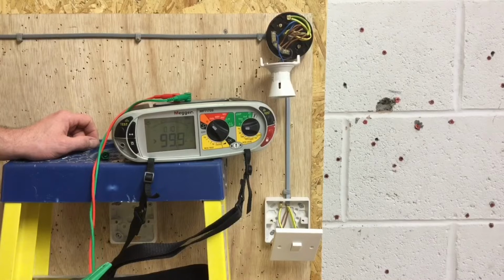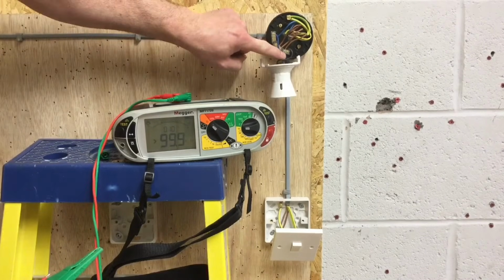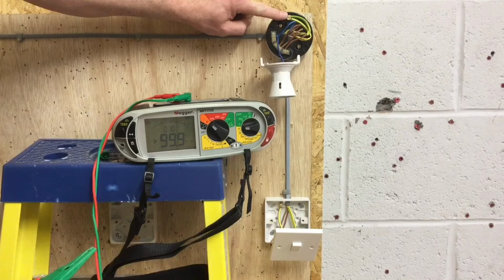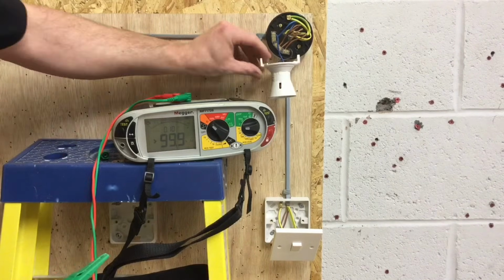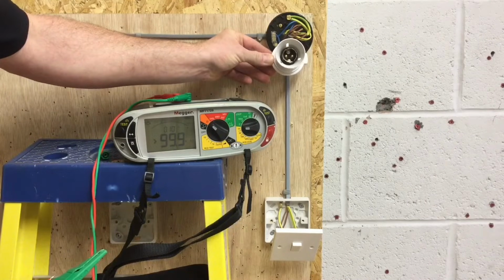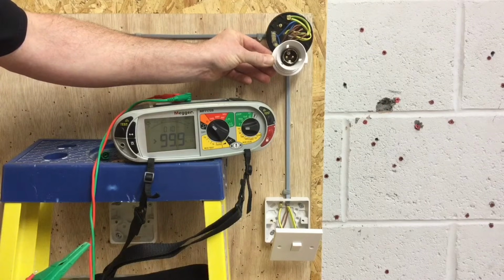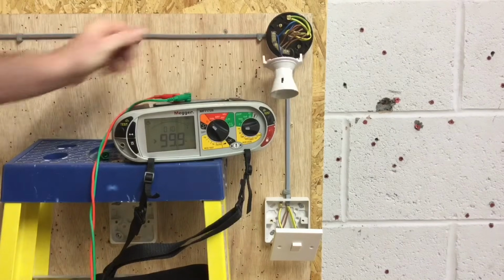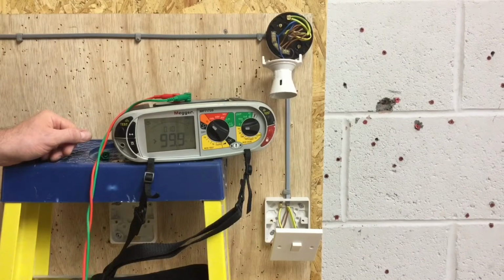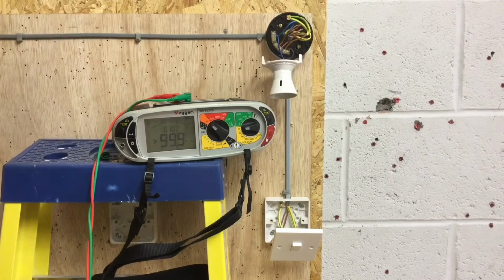In this case we only have one lighting point. So we're going to go to that lighting point and connect between the switching line and the earth terminal where the CPCs are connected. Remembering we're only on week 6 with my learners and it is a bayonet cap lamp holder. We know as we move forward that if this was an Edison screw, we'd need to prove the polarity from within inside the lamp holder itself, making sure the centre pin is line and the screwed part is neutral. We're at a stage where we're just introducing testing.